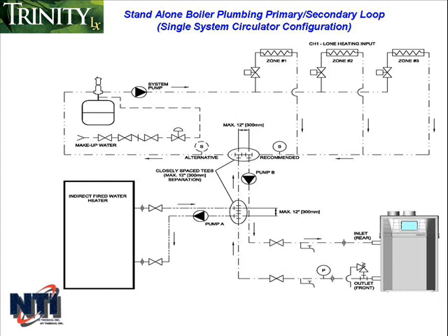The LX actually has 3 options when determining which water temperature you want the boiler to modulate itself to. The factory default is the outlet temperature, which means the boiler will watch the temperature of the water at the boiler outlet and will modulate itself to maintain the temperature at the outlet at the target water temperature. Other options are either the inlet temperature or the system temperature, and the choice can be made within the controller settings. If the inlet is chosen, then the boiler will watch the inlet water temperature and modulate itself in order to keep it at the target water temperature.